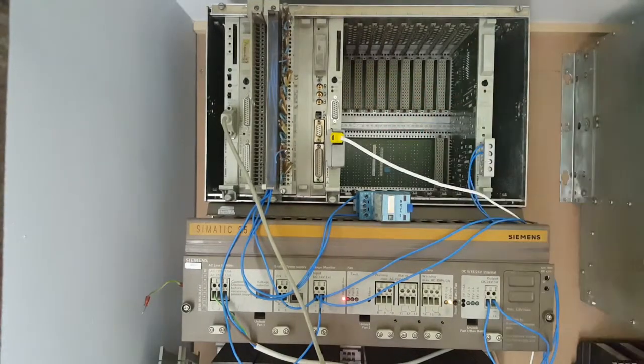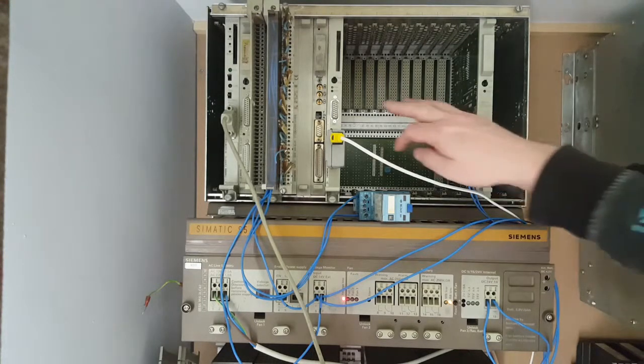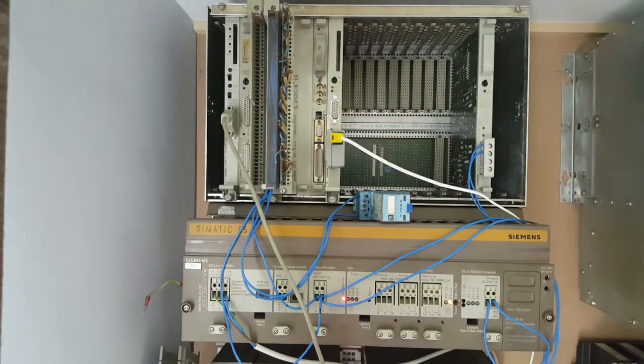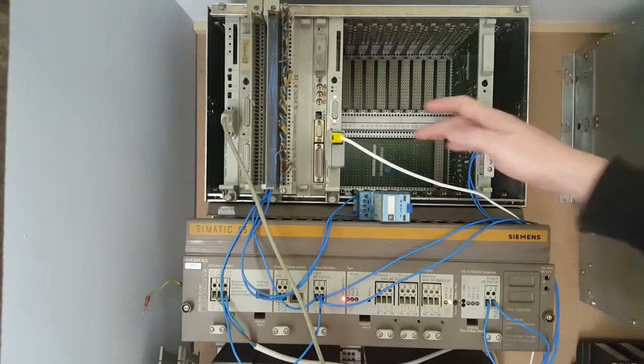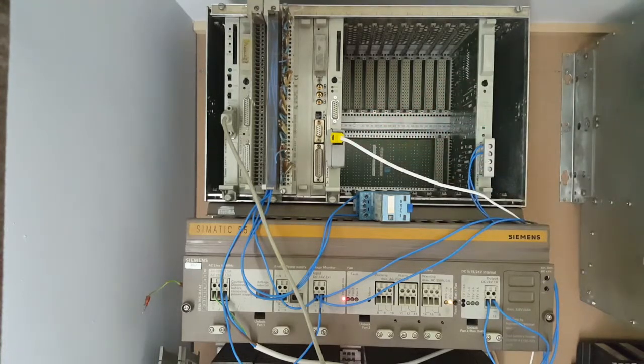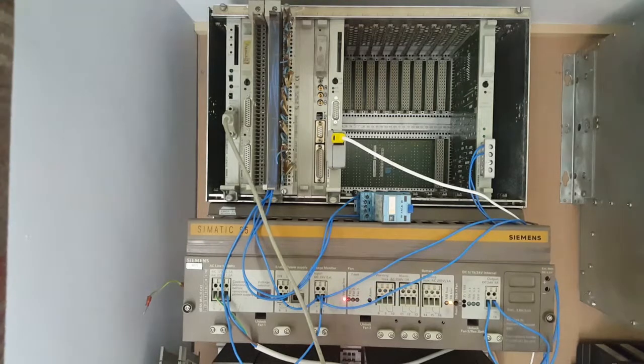This slot on the front of the card is for a flash memory module. The memory module will hold the parameters for the card in the case of a power failure and a flat battery. This 15-pin port here is marked as prog. This is for the programmer to connect to for parameterization. Here we have another 15-pin port, marked as AUI/TP. This is where the card would connect to the H1 network.